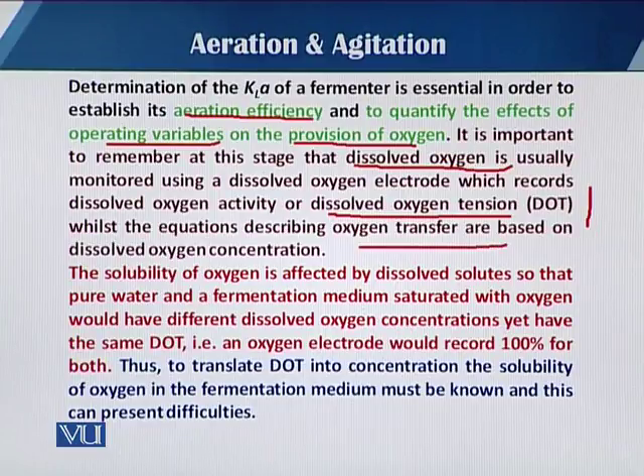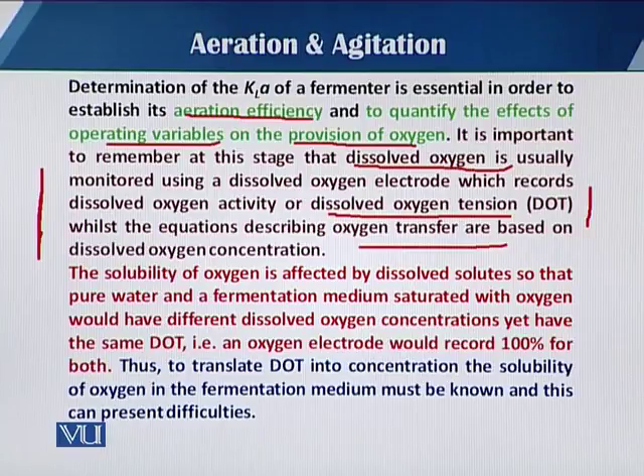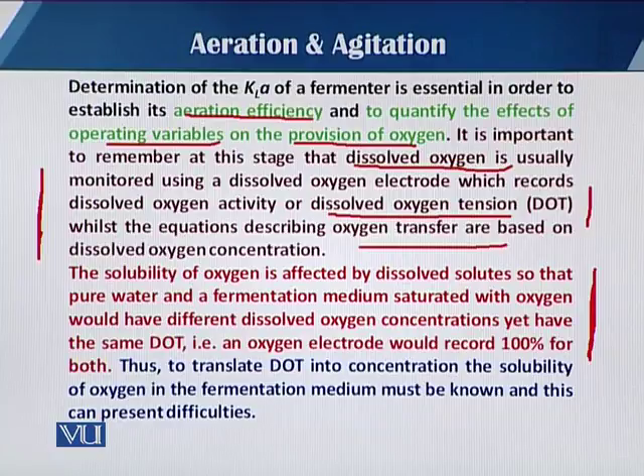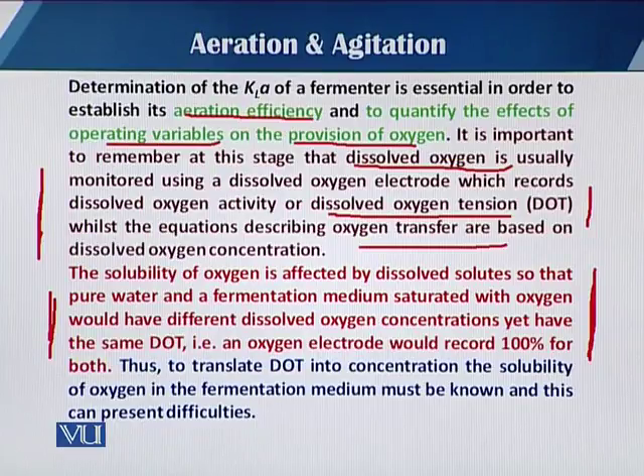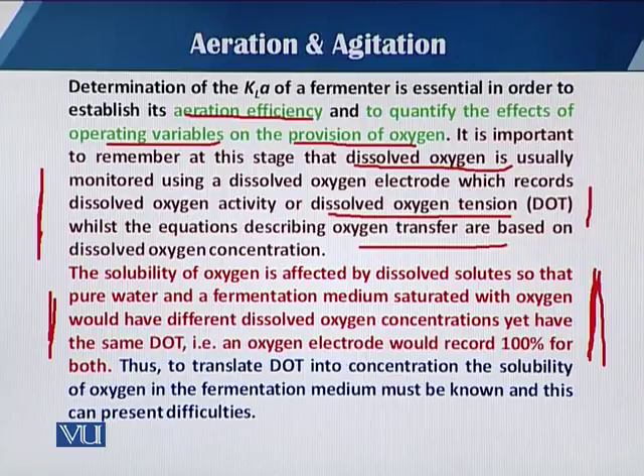If we describe the oxygen transfer based upon the dissolved oxygen concentration, the OTR and DOT are very interlinked. The solubility of oxygen is affected by the dissolved solutes, so pure water and the fermentation medium saturated with oxygen would have different dissolved oxygen concentrations yet have the same DOT. The oxygen electrode records dissolved oxygen, mostly calibrated to 100 percent solubility.